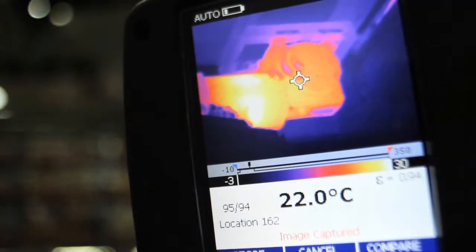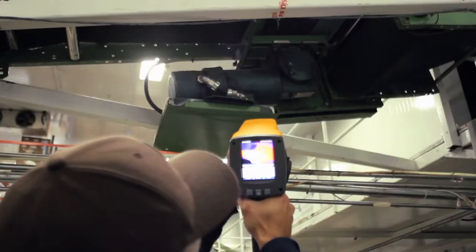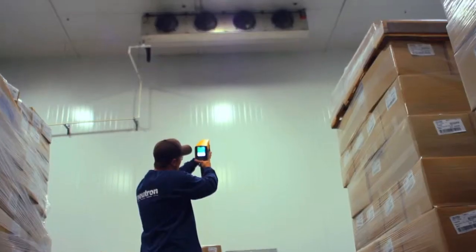One of the benefits of thermal imaging is that it allows us to see temperature distribution throughout our electrical equipment as well as refrigeration and building envelopes. We can use that to see if our customers are having heat loss in their refrigeration areas or if motors are starting to wear out, bearings, etc.